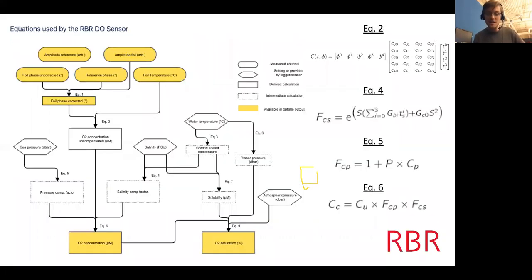Next slide, Eric. So the full processing pipeline of the ODO sensor goes beyond applying just the polynomial calibration model and the linear adjustment, and it's depicted here in this block diagram. So the raw measurement is essentially this phase value here, and that in conjunction with the foil temperature, we produce the concentration of O2 using the calibration polynomial.